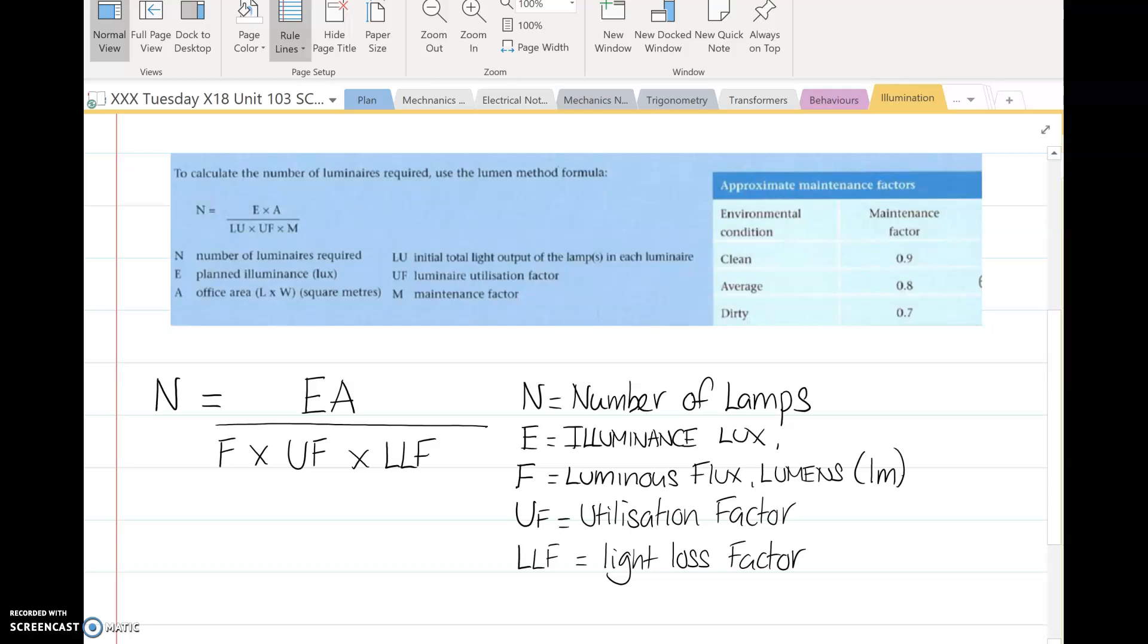So in this video we're going to explain how to calculate the number of lamps within a room area to provide an illuminance on the surface. Basically what we have in this formula is N, the number of lights, equals the illuminance times the floor area divided by the actual luminous flux of the lamps that you fit in, the utilisation factor, and the light loss factor.